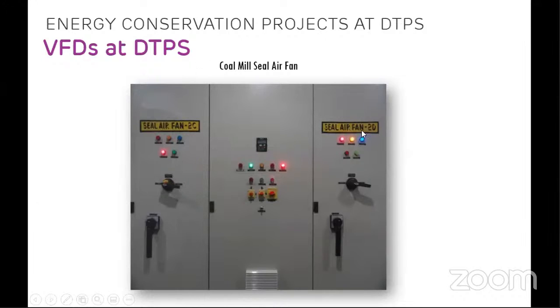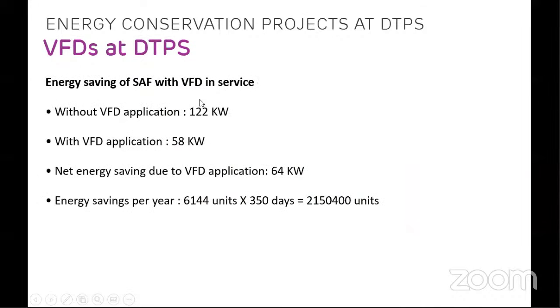There are two seal air fans for coal mills, and one of them is running and one is standby at every instant. So we installed a common single VFD for both these applications. The motor consumption before VFD application was 122 kilowatt. With VFD, it consumes as little as 58 kilowatt. You can see it is almost less than 50% of loading. The net energy saving is 64 kilowatt.